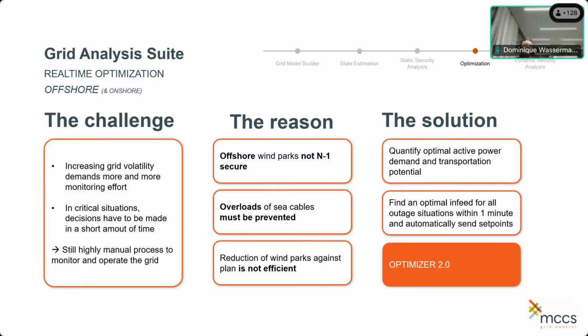But why do we even need to work on offshore wind parks or optimize them in the first place? First of all, offshore wind parks at 50 Hertz and Elia are not N-1 secure by definition. That means the cables that connect the offshore wind park to the onshore grid do not suffice, or they only suffice if they are all available, in order to transport the entire energy produced by the wind park.